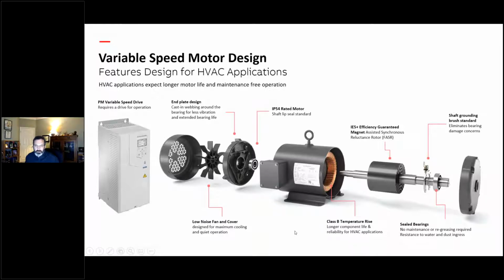And that's the other thing. If you think, what does a cooler running motor also get me? Well, it's a class B temperature rise in these systems. The standard induction motor is class F rise. So they run about 20% hotter. So that's shorter life in your insulation system. That also degrades your grease life. And by having a class B temperature rise, you can also put a smaller cooling fan on these, and that's why they run at a lower dBA noise level. So it gets you a quieter motor from a design standpoint too, because you can capitalize on these lower temperatures. The IP54, pretty much anyone can do that with any of those motor technologies. I just put it in here because that's kind of the standard.